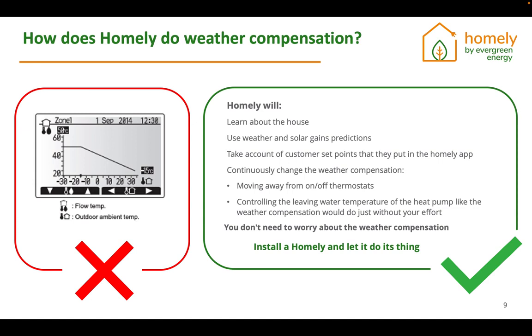From the customer's perspective, there would be no weather compensation curve. It would just be flow temperatures constantly changing through Homely. Every half an hour, Homely will be updating the flow temperature set point on the customer's heat pump, and that's what they would see on the actual heat pump controller. So this is moving away from on and off thermostats. We can also turn the heat pump on and off in certain circumstances. Let's say you're cooking and the internal temperature rises quite a bit, then Homely could turn the heat pump completely off. But in most cases, what we'd like to see is the heat pump continuously running in the background at very low flow temperatures, achieving those best-in-class efficiencies and achieving the customer set points.